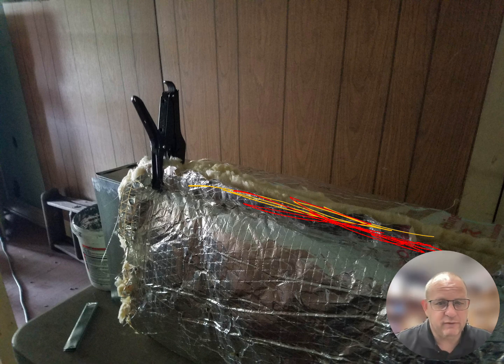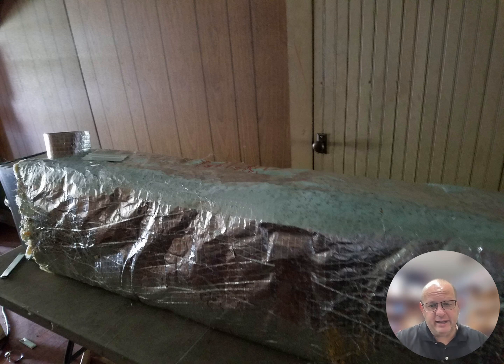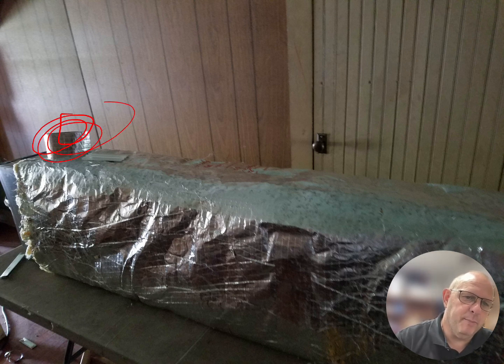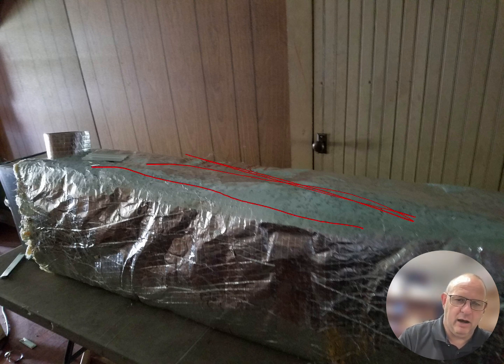Put the foil tape on that hole to maintain the vapor barrier of that ductwork itself. So I'm going to take that seam and staple it all the way down that insulation. After I get done stapling that entire seam, I am going to fold that seam over the ductwork, and I'm going to use foil back tape. There are many different types out there; you have to see what your manufacturer wants you to use. And I'm going to fold it and put that tape on the seam all the way down that particular insulation.